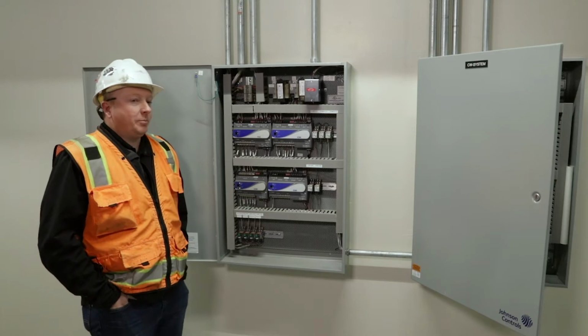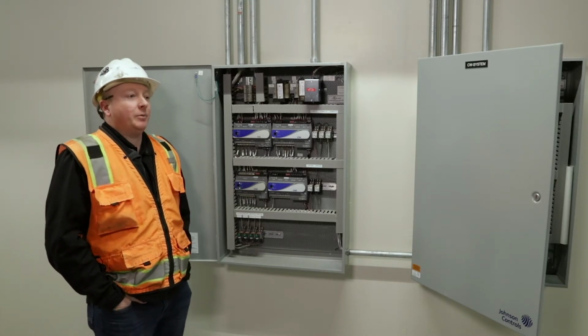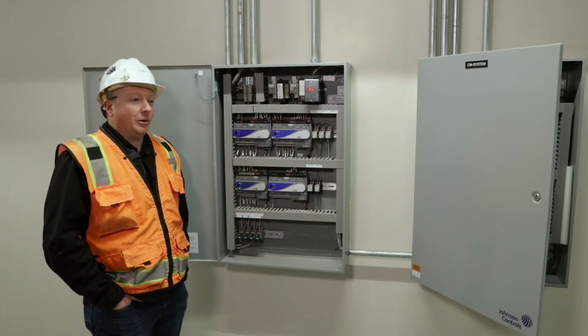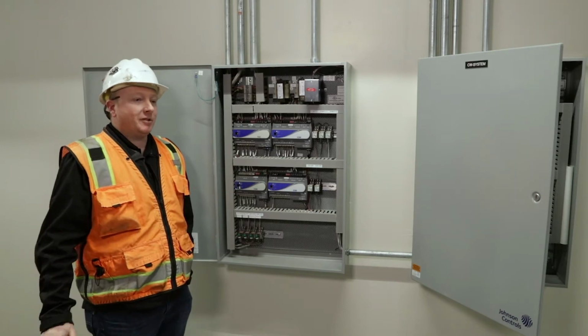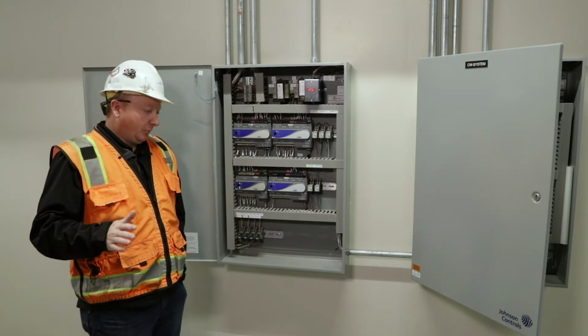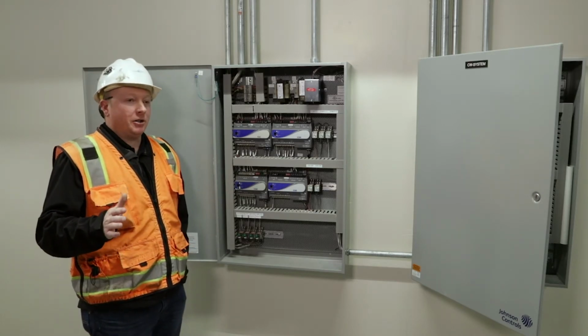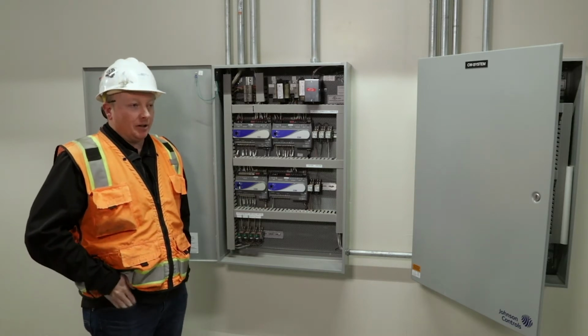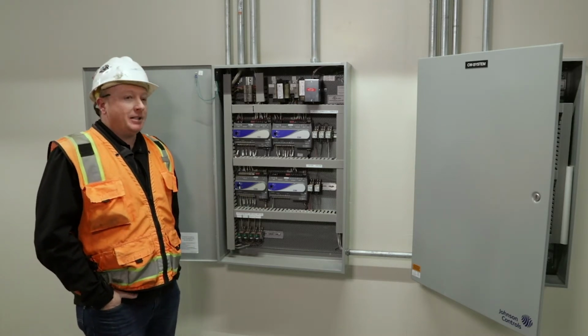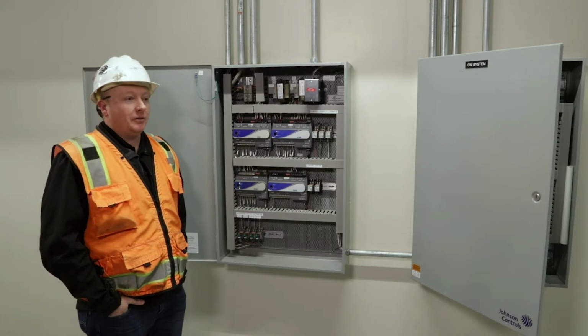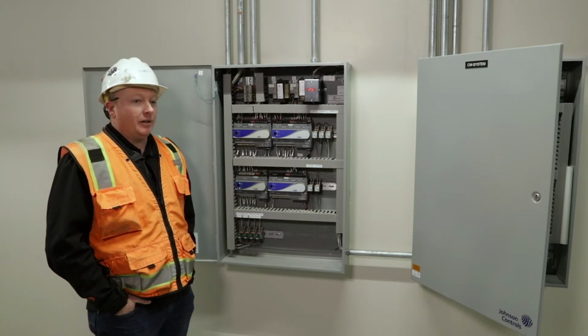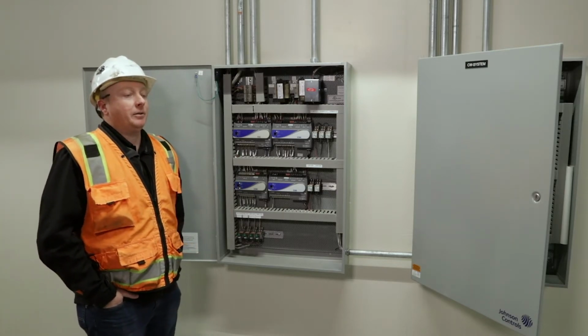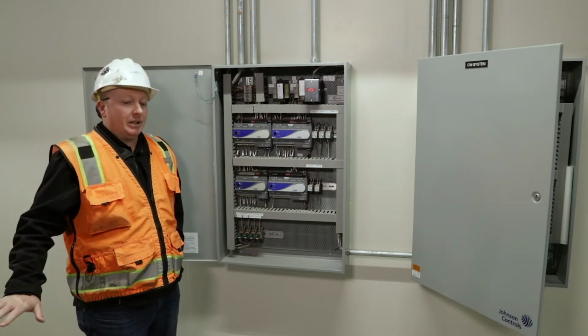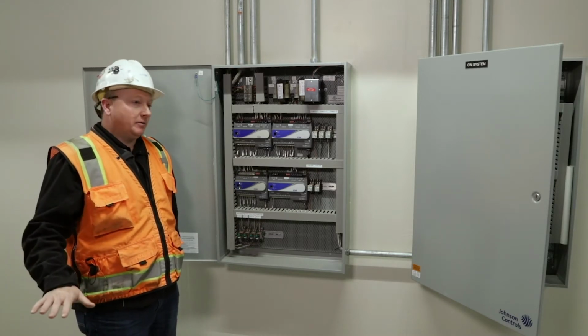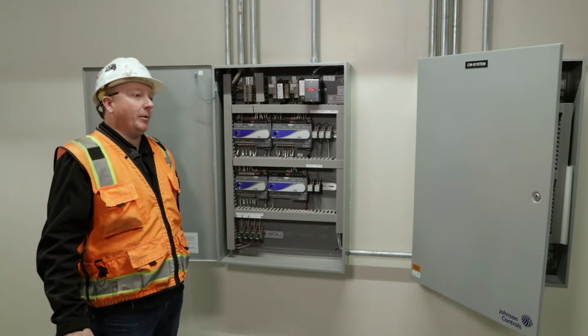Okay, so we'll pick a primary pump and a condenser water pump with the lowest runtime anytime we start a chiller. We have isolation valves on each chiller, one on the condenser water side, one on the supply side. And then out at the tower, we have isolation valves on supply and return of each cell. So once we start a chiller, we start a condenser water pump, a primary pump.